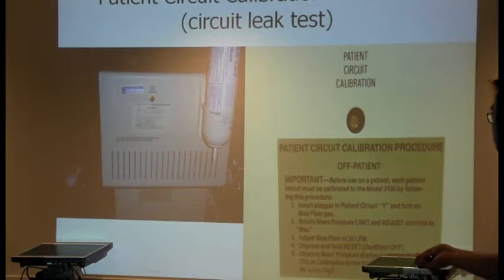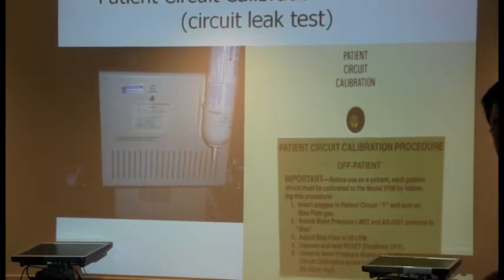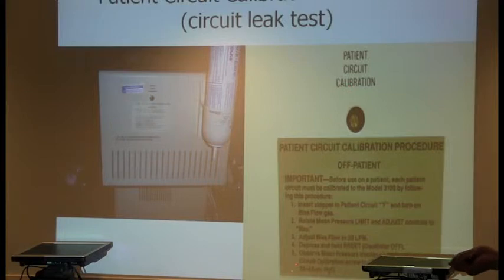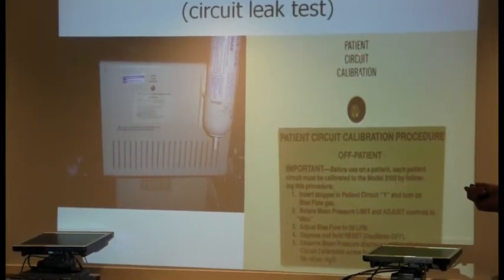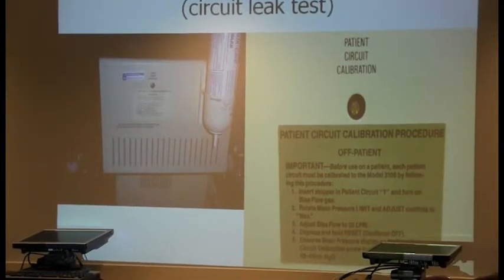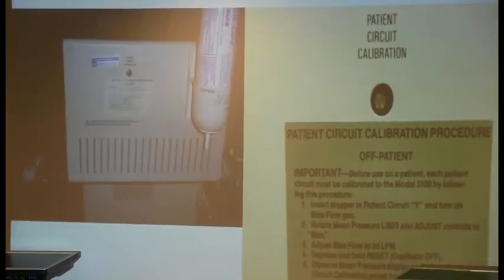So that's what that test is. Any questions about that? Okay, no, good. All right, good. So the micro leaks: if it's 37, 38, you want to adjust your patient circuit calibration screw to 39 or 40, and then you're good to go.